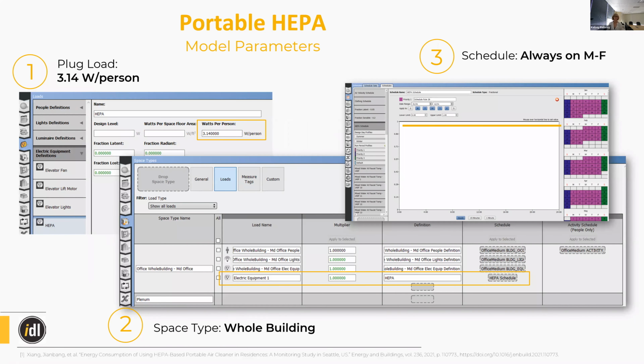As far as modeling HEPA filters goes, we modeled it just as a plug load. Some of the research we did averaged out at 3.14 watts per person. So we put that plug load into the energy models. I'm showing you here the medium office building prototype, just because it's a relatively straightforward HVAC configuration. We use the HEPA filter just in the main office space, and we have it on all the time, 24/5, because it's just Monday through Friday. And yeah, that was a pretty simple energy model as well.